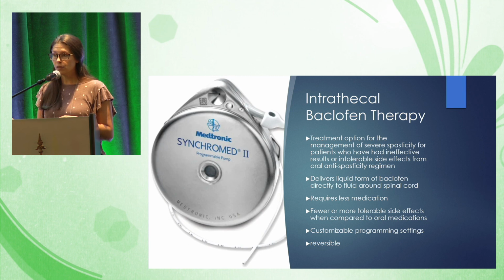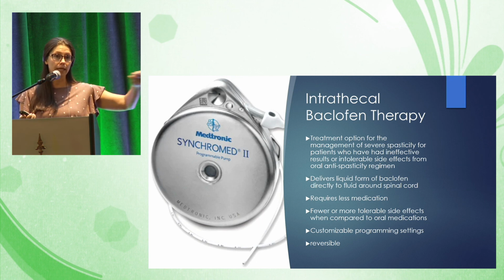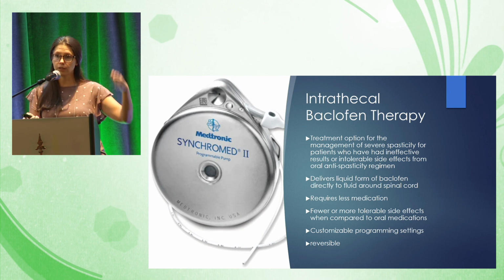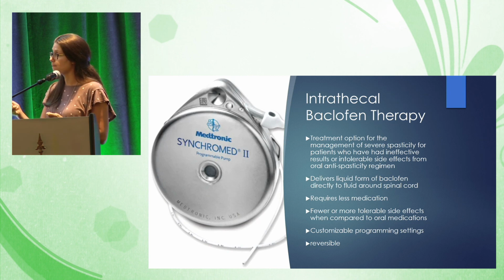With the pump itself, we can be pretty customizable to what a patient needs. So with the pumps, you can deliver a pretty continuous rate in the spinal fluid, so you have a pretty steady rate of drug. You can also flex your rates, so you can give somebody more medication during the day, less at night. You can give boluses throughout the day. There's also ways that the patient can use, if you're familiar with like a PCA, they can use it sort of like that, where they can deliver their own bolus as well.